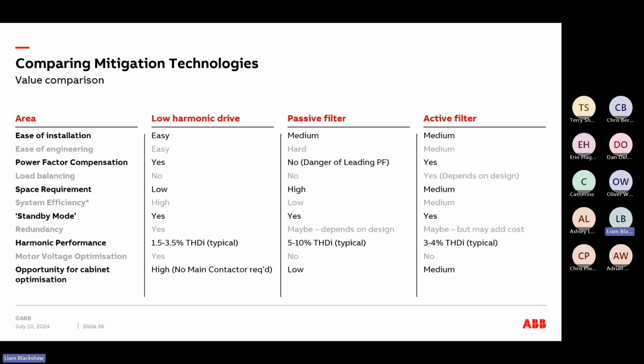And that's quite an interesting one, where when we look at redundancy, depending on design, it may add cost as well. If we look at an active filter in particular, you need to have a spare active filter typically on site, because if that active filter malfunctions or breaks down, it's out of action. And because that's being used to cancel out harmonics, your harmonics could go back to high levels again, high enough where it starts to cause problems on the system. So you need to have a spare available to accommodate for that, at least anyway.